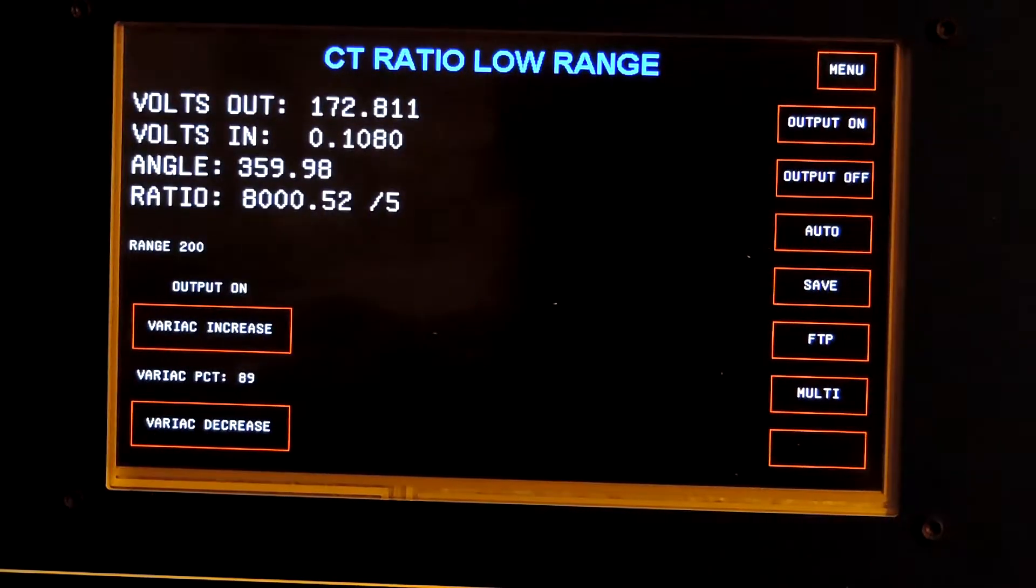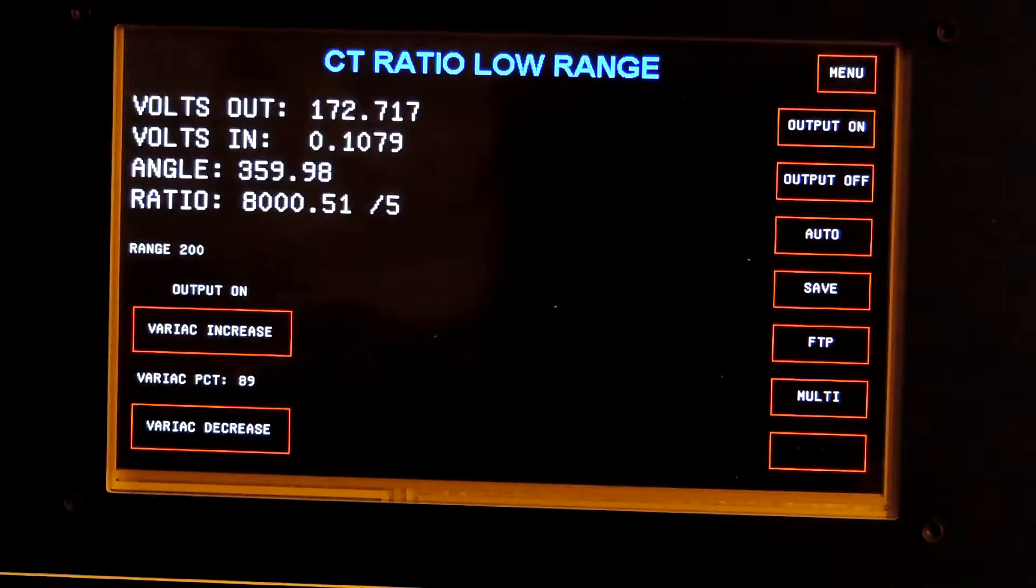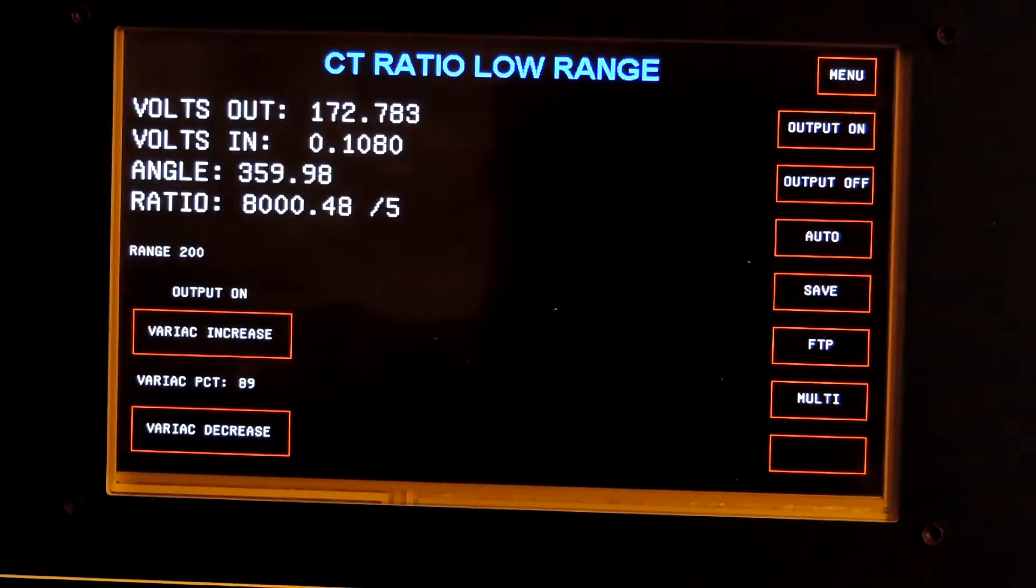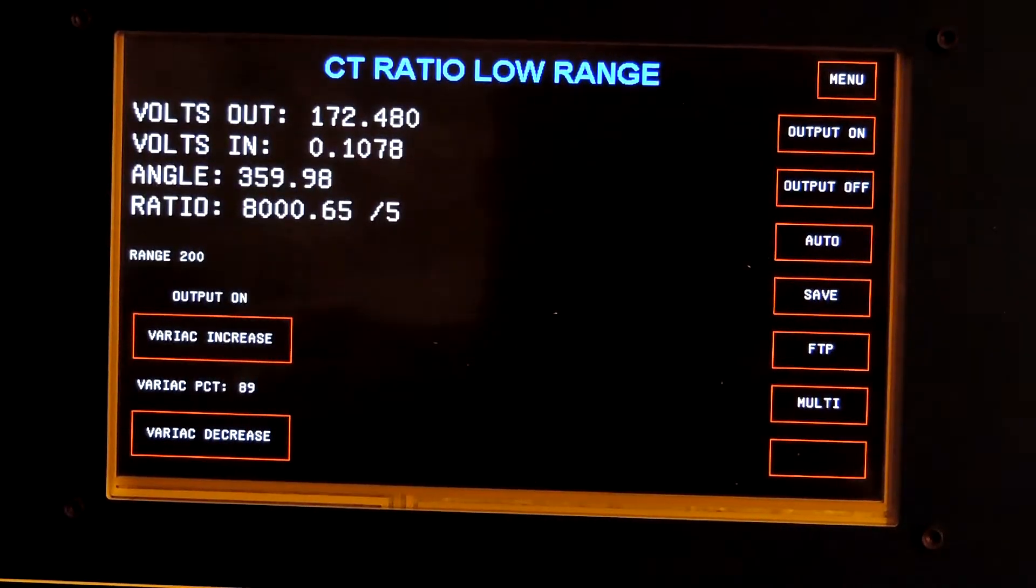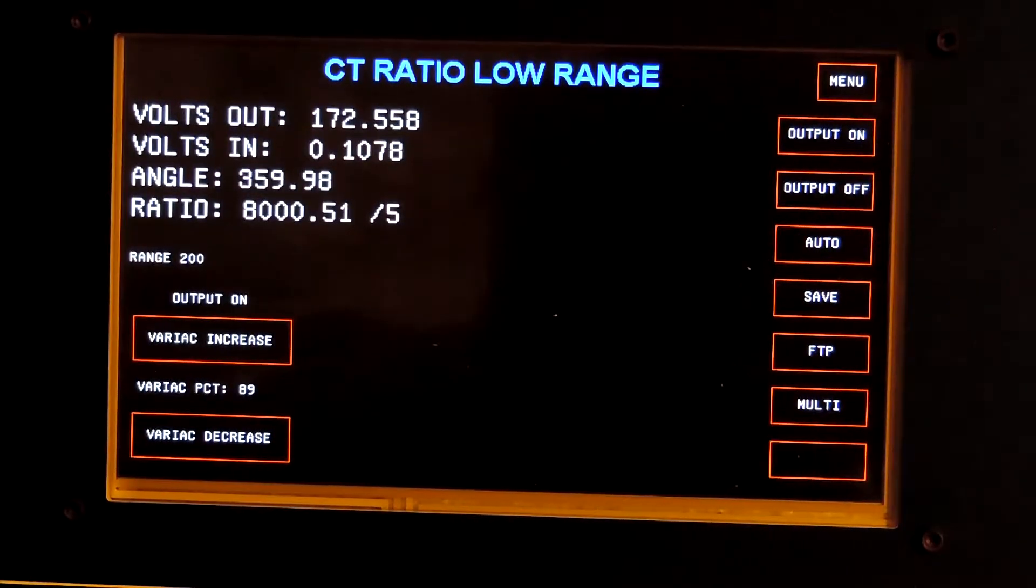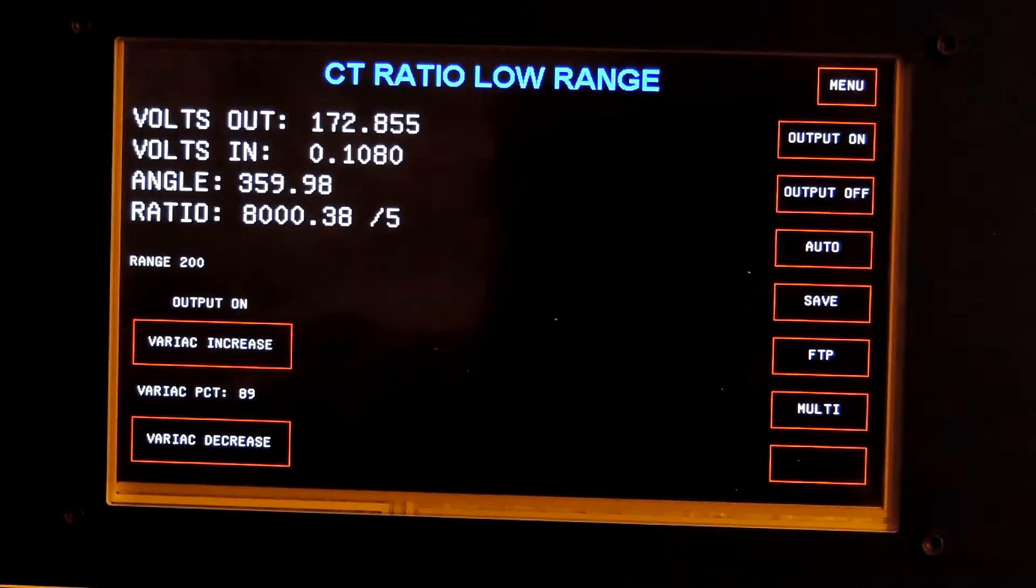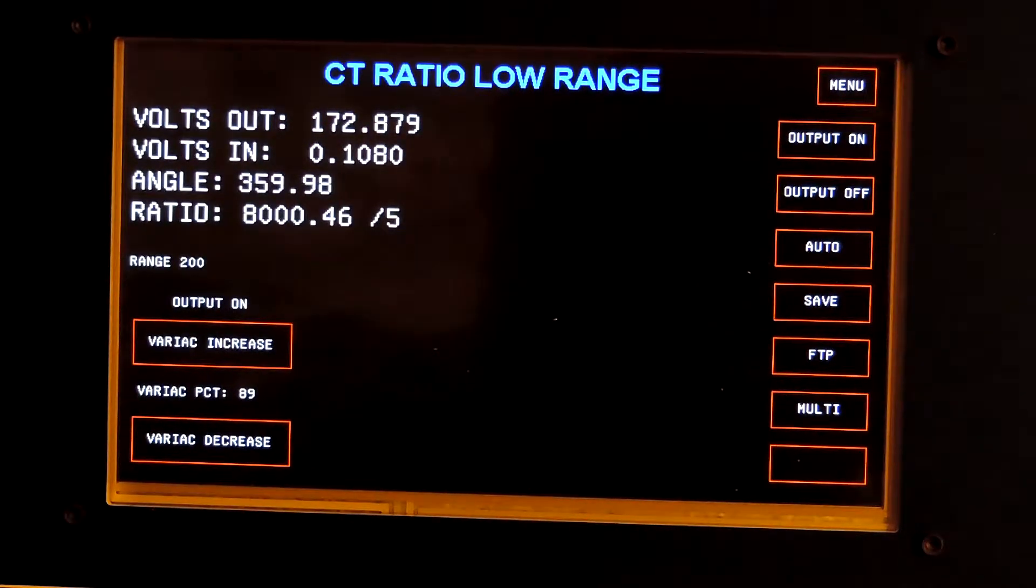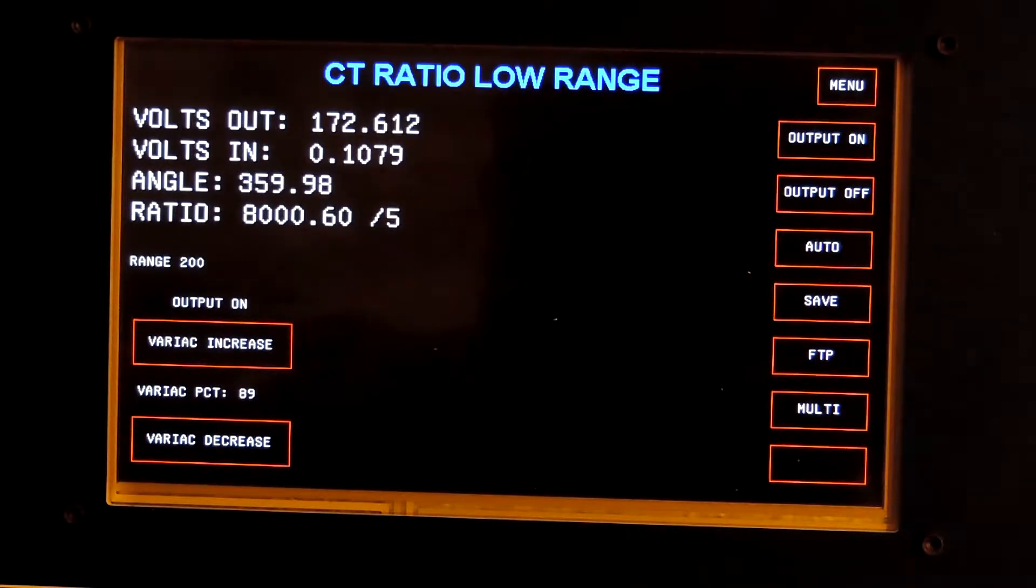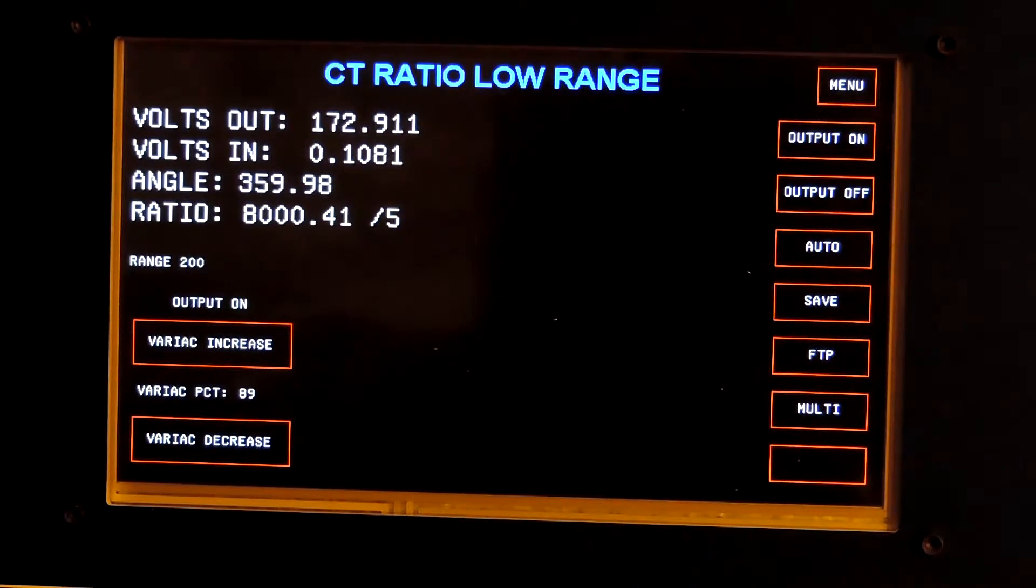Now, this is an 8,000 to 5 standard. As you can see, the ratio reads out within about 0.0125%. It's very stable within that tolerance.